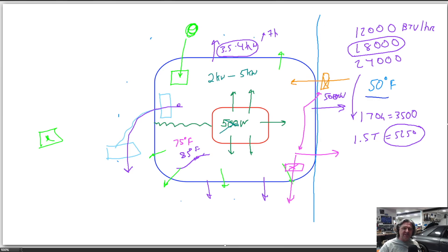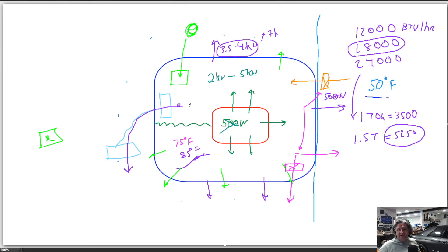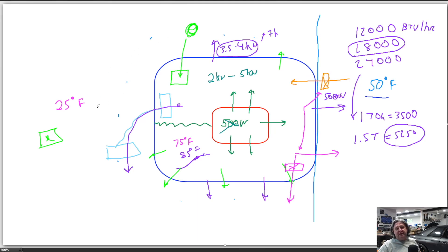One thing to consider about running an air conditioner for a server room is that it runs all the time. Mine has been running continuously for three years with just two maintenance checks. It runs 24 hours a day, 365 days a year, which means a lot of wear and tear. More importantly, it runs when it's very cold outside — here in winter it might get down to 25 degrees Fahrenheit, and in other parts of the U.S. it could be zero or even minus 10 degrees, and you're still running the air conditioner because the servers are still producing heat. If you have a large enough air intake you might bring in enough cold outside air to avoid needing it, but in most cases the air conditioner will still be running.